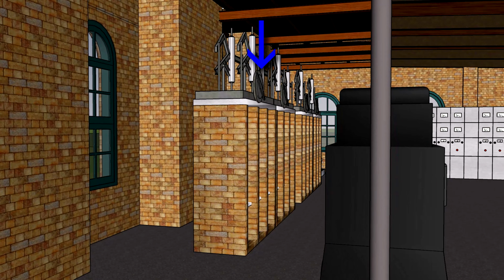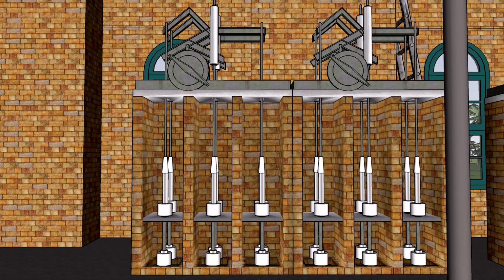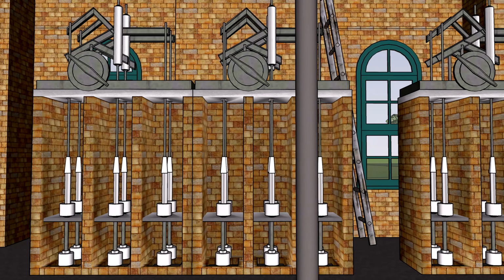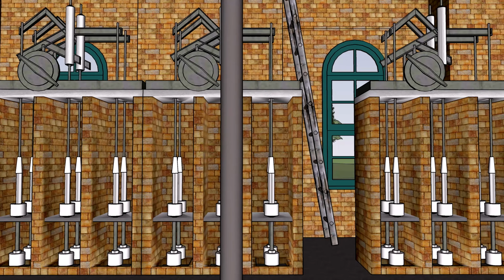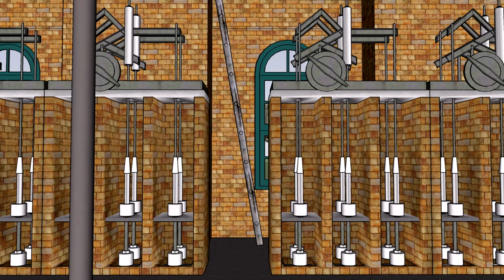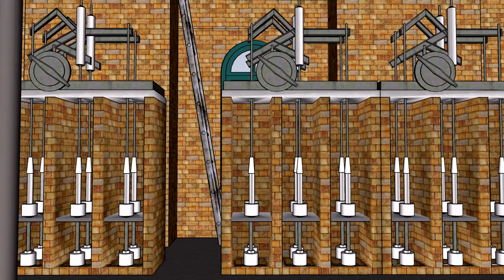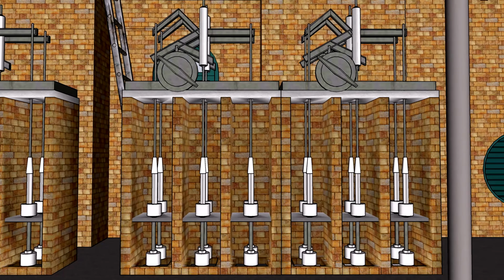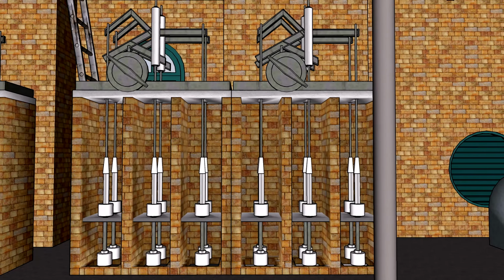Recall that the oil switches were the first piece of equipment that the high voltage lines would have traversed coming into the station. Doing all of the current switching on the high voltage side of the substation was somewhat revolutionary at the time, as switching was typically done once the current had been stepped down. But the AE&C design leveraged oil switches to safely manage the high voltage switching, which is actually the better place to do the switching from a maintenance point of view.